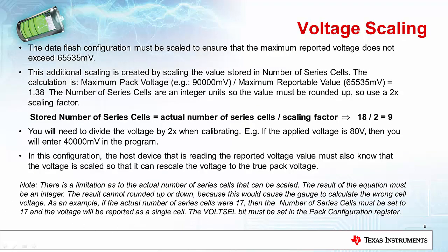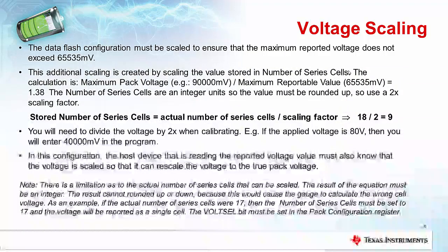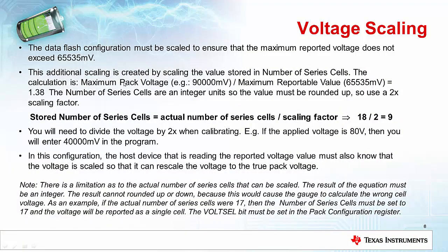In voltage scaling, you also have to modify some of the flash parameters. So we have to make sure that when the gauge is calculating the voltages, it doesn't calculate a reported voltage greater than the supported 65.5 volts. In order to do that, we modify the value stored in the number of series cells. So in this case, say we had 90 volts maximum, versus our reported value can't be more than 65. That's a value of 1.38.